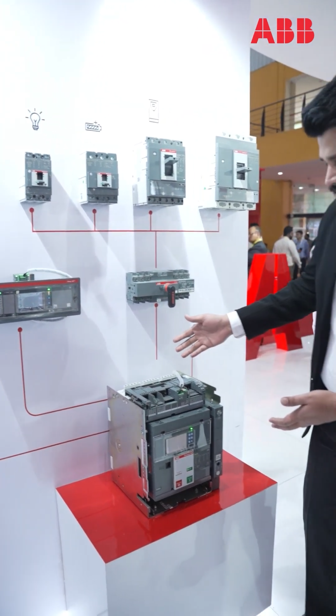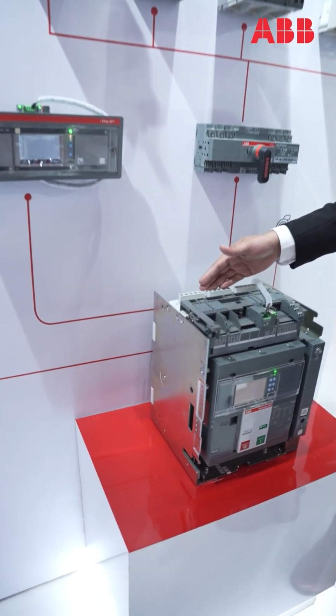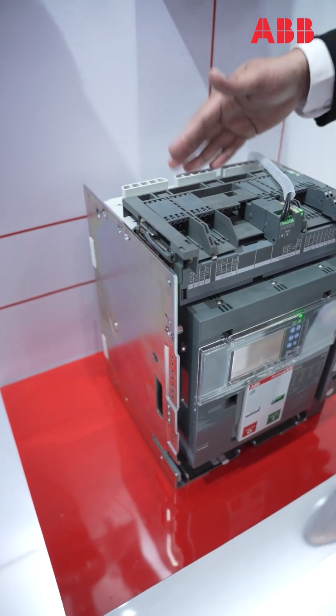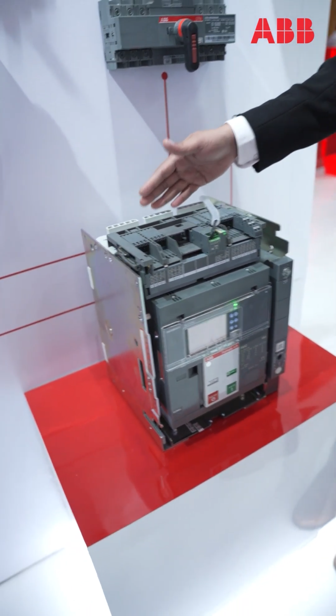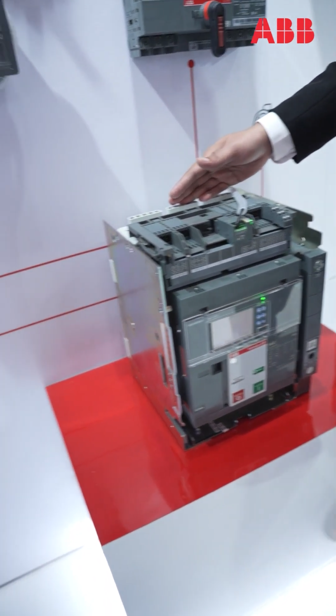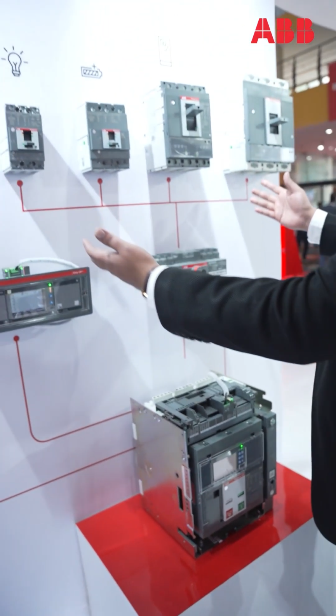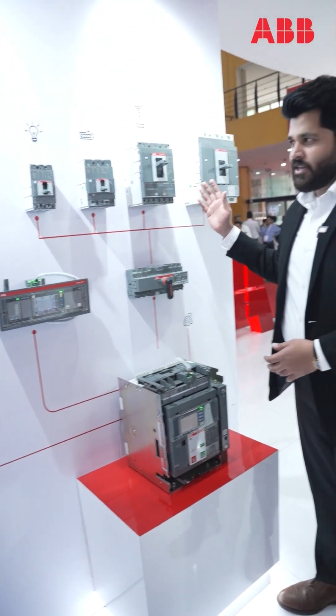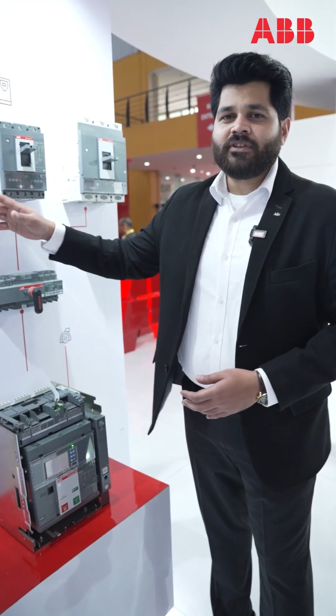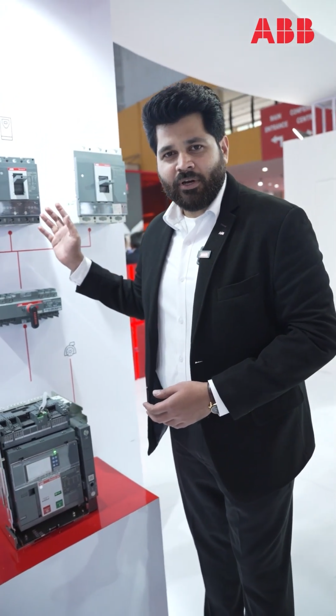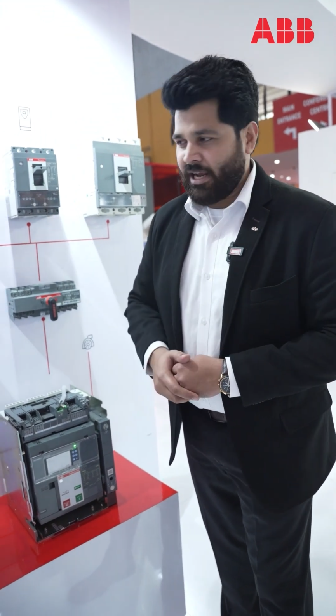Here you can see we have the latest generation of air circuit breakers, which we call the Formula series, which is majorly intended for building and utility applications where 50 kiloampere is needed up to 440 volts. And then we have the Formula range of MCCBs, again up to 800 ampere, which is divided into 4 frames. These also have the highest breaking capacity of 50 kiloampere, and are majorly for thermal magnetic applications.